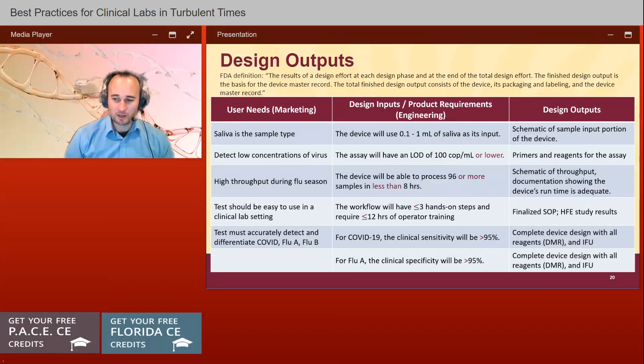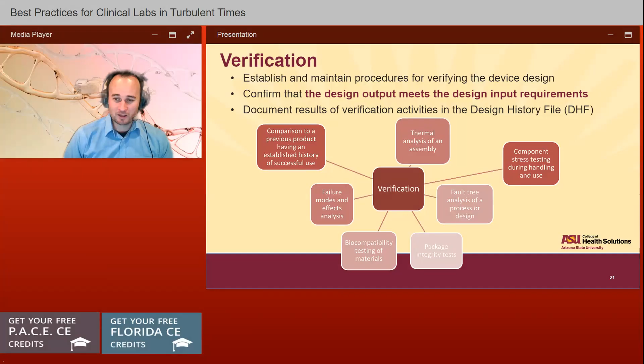Next, we go to verification. What does that look like in a clinical lab? Well, it could be a failure modes and effects analysis, a thermal analysis of your assembly. It could be a fault tree analysis, package integrity tests, comparing your lab test to a previous lab test that has an established history of successful use. So these are things that you can do to verify that your lab test is meeting the specifications that you set forth.